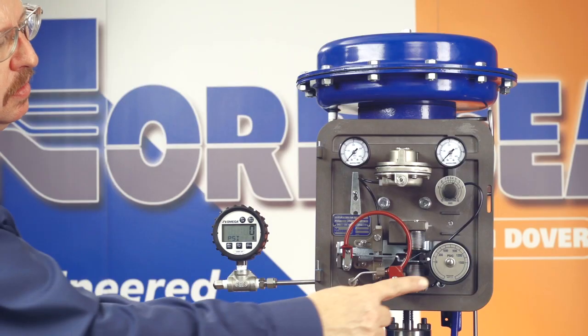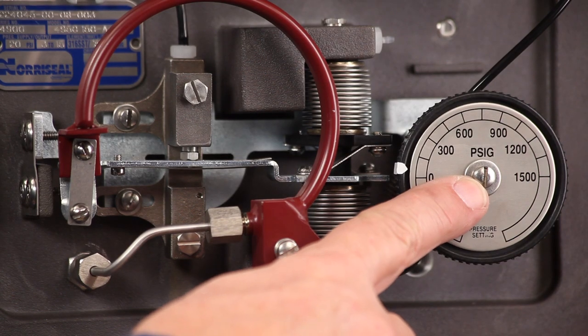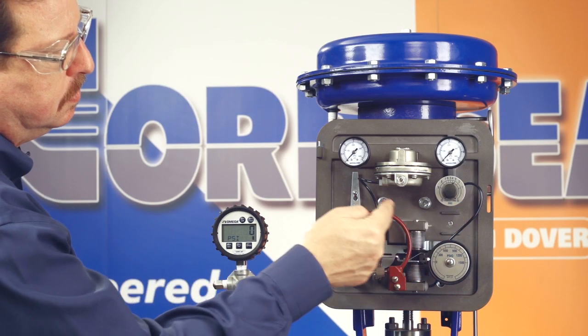If a Bourdon tube with a different range was installed, it's also necessary to replace the pressure setting knob scale. Just remove the machine screw and install the new scale. Check all tubing fittings and the Bourdon tube machine screws for leaks, and tighten them if needed.